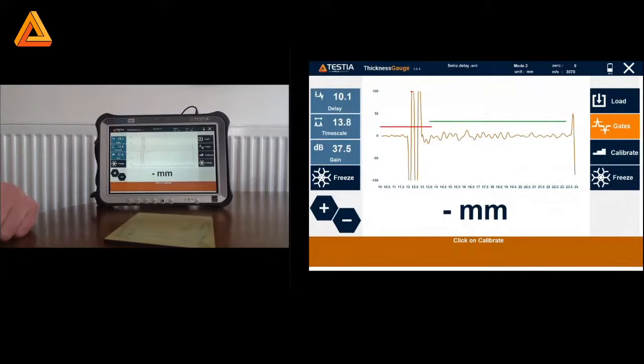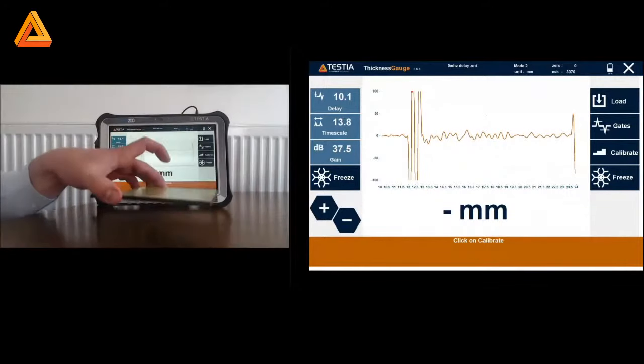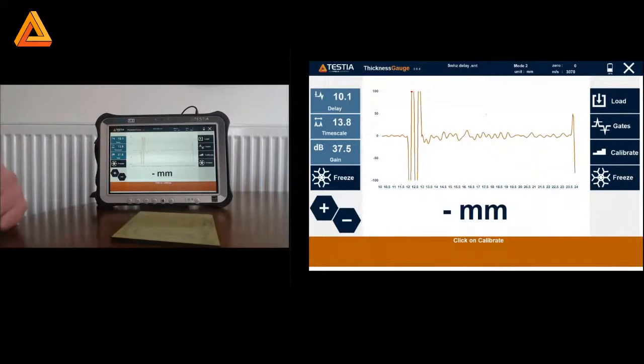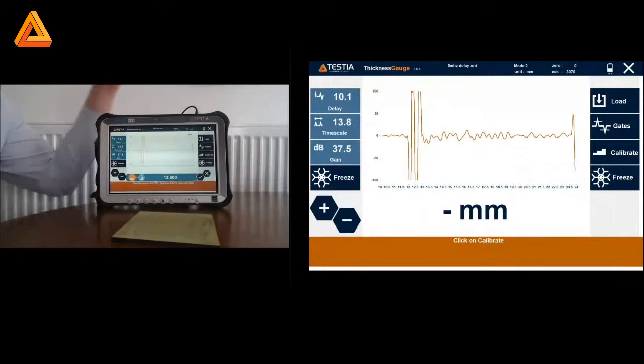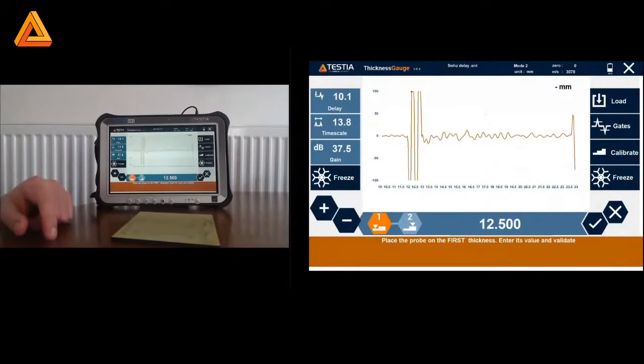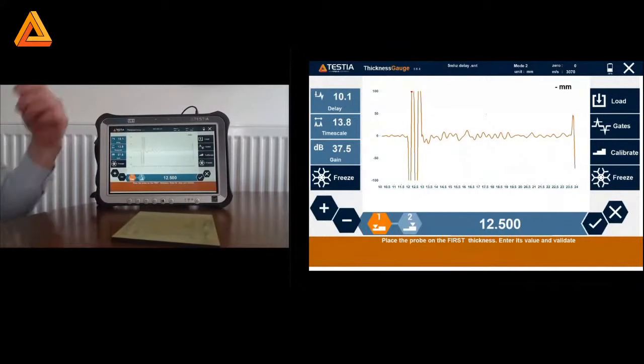Now, because we've already programmed this inside the flaw detector module, we already have the velocities calculated on exactly the same part. If we were to perform a calibration, the instrument would ask us to perform a two-step calibration, and it takes us on a step-by-step walkthrough through the process.